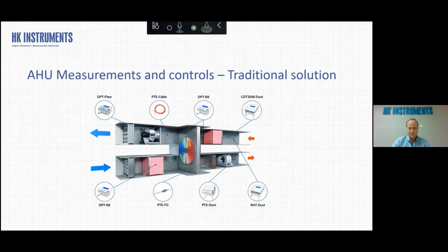And then we have other parameters we can measure, like temperature, which is very basic. We have passive temperature sensors for duct and or cable, and then we have new ones now that are coming up. It's for liquid, so we can also measure liquid, for example heating coils from the unit. And then also these indoor air quality parameters, for example CO2 or humidity from the duct.